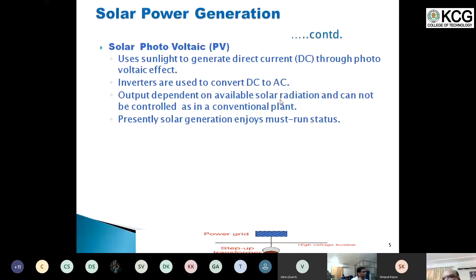If there is an issue in the transmission system that endangers grid security, these plants will otherwise enjoy must-run status. Here is a simple schematic: you have the solar panels, and depending on your configuration, the panel used, and the DC voltage and current you're getting, you arrange them into tables. The tables run through junction boxes to the inverters, then a step-up transformer connects to the grid. Depending on the size of your solar plant, you can connect it to 11 kV, 33 kV, 220 kV, or 400 kV. Now we are having plants connecting at 220 kV or even 400 kV.